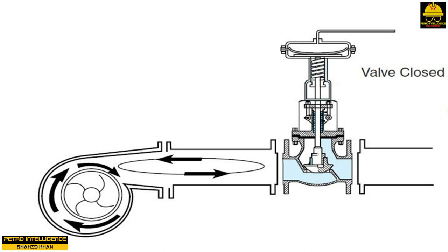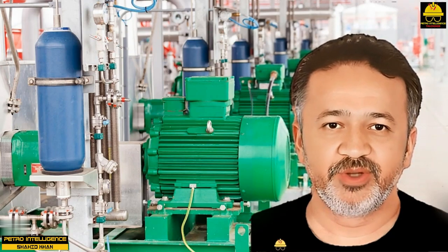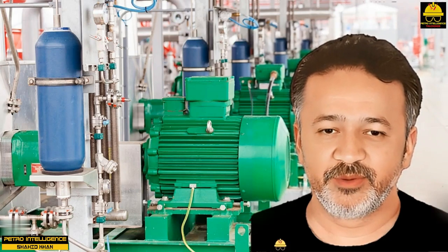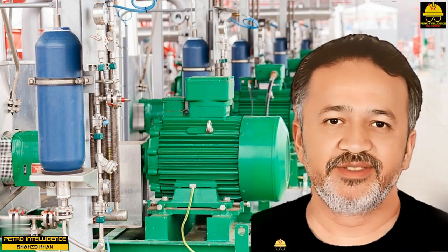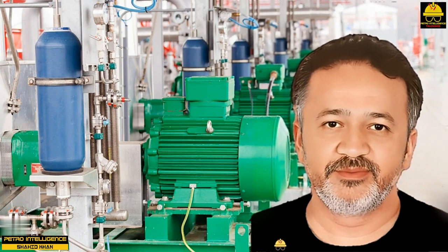Fluid friction within this area begins to heat up the liquid. Operators should keep this principle in mind if the liquid being pumped is close to its boiling point. When the liquid vaporizes, it expands and gets hot. This process can create tremendous pressure that will damage the pump.